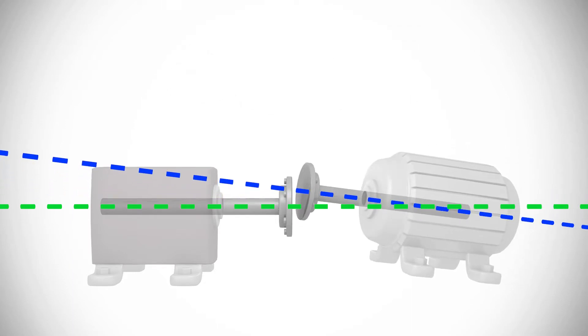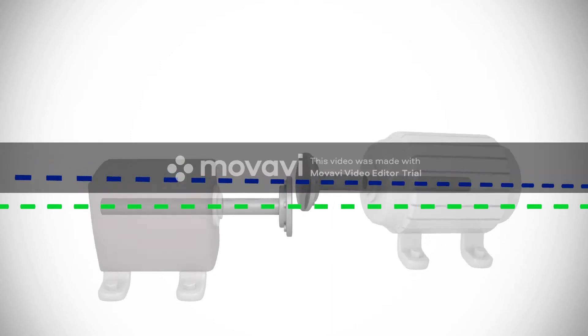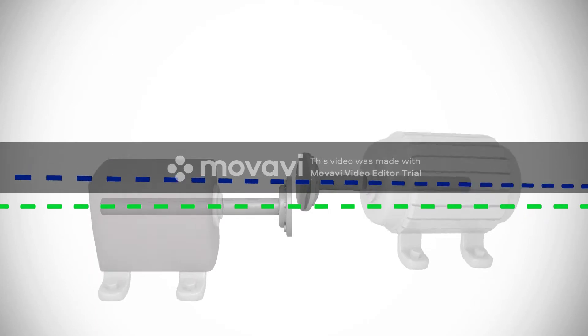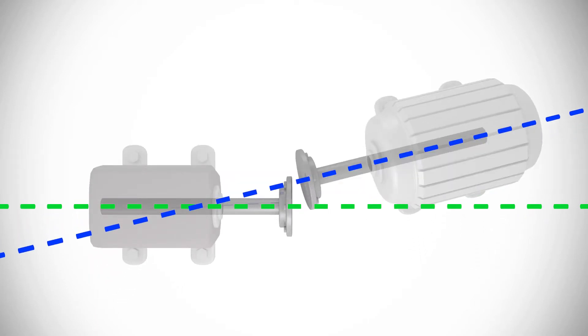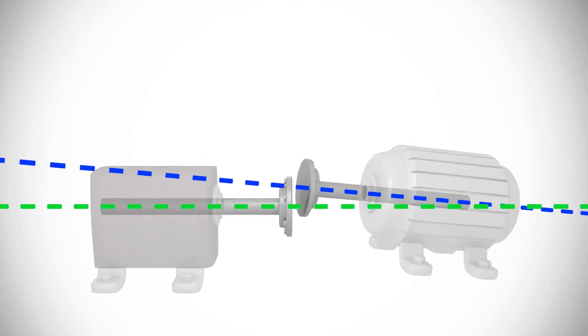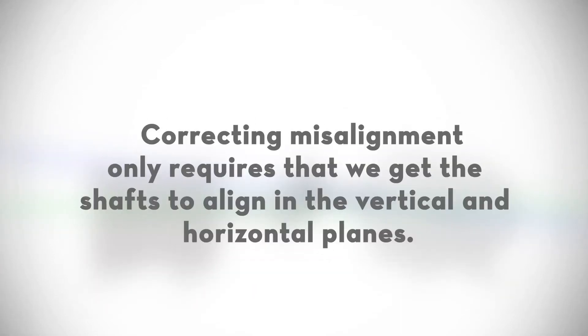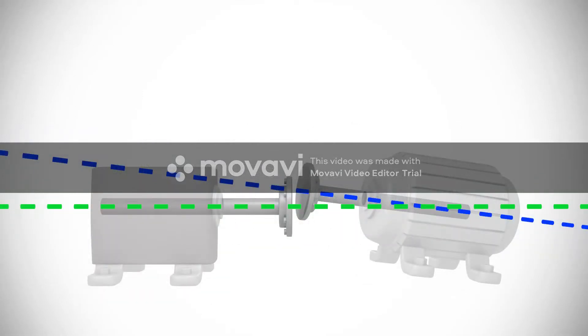What we usually see in the field is a combination of both offset and angular misalignment occurring in three dimensions, as you can see here as we rotate between the vertical plane and the horizontal plane. While it is much easier to understand misalignment if you can visualize it in three-dimensional space, correcting misalignment only requires that we get the shafts to align in the vertical plane and in the horizontal plane. Fortunately, we are able to adjust the relative position of the two shafts in these two dimensions.